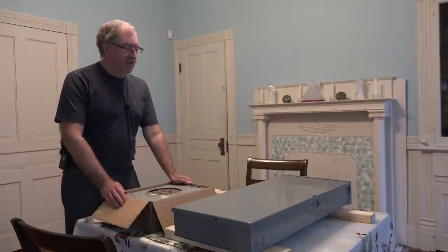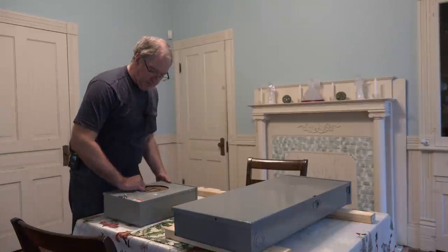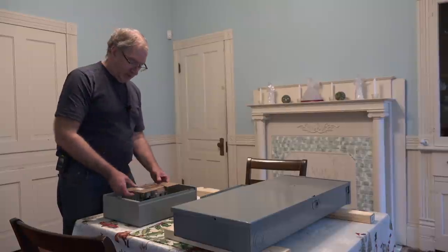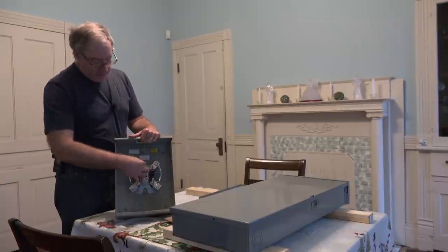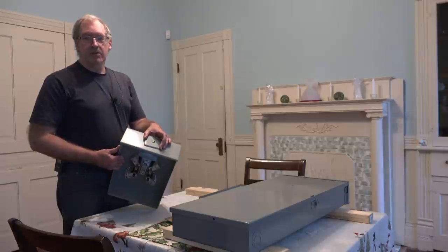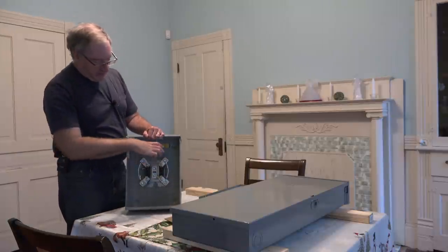Was going to mount the meter box outside today, but it's raining, so just doing prep work. This is the meter box — it's very important because that's where power comes in from the utility. The meter plugs in here at four heavy-duty contacts, and these clamps hold the meter in place. You can bring cabling in from overhead with a mast pipe going straight up, a weather head on top, and the utility always comes in from the top. There are also knockouts for adding conduits.